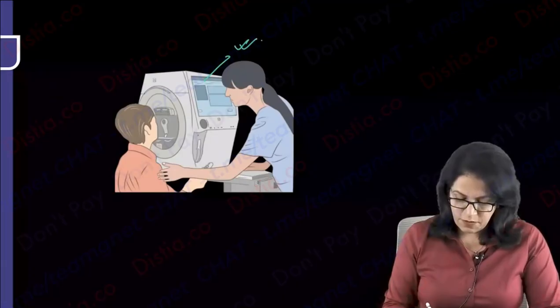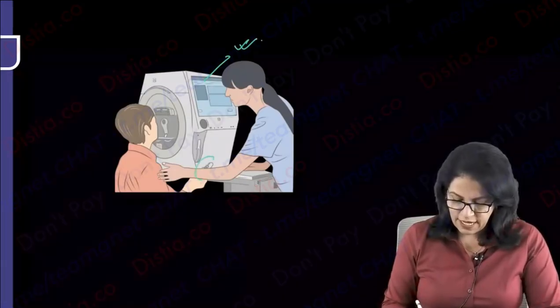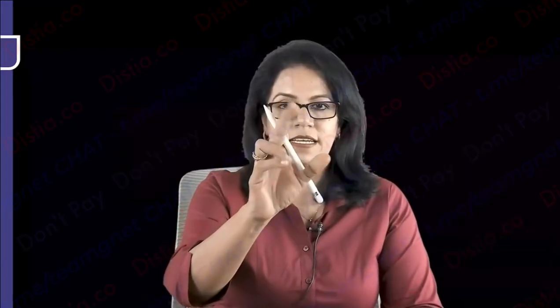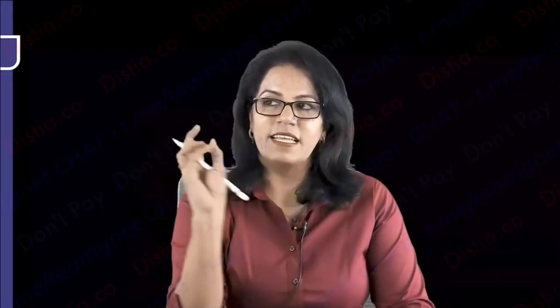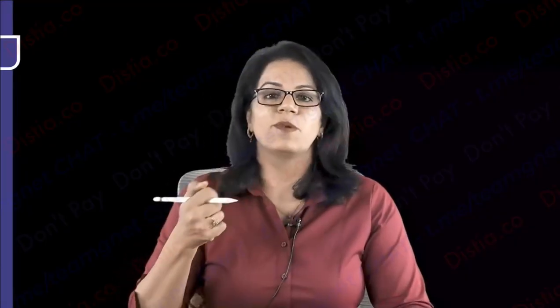We keep the chin of the patient here, he has a button in the hand, right? One eye closed, now he is focusing on the central white target and then there is a bowl shaped screen here, like a bowl. And there are multiple white lights there. Whenever he feels any light is on, he has to just press the button. He has to keep looking straight only, but whenever any light is on, he will press the button.